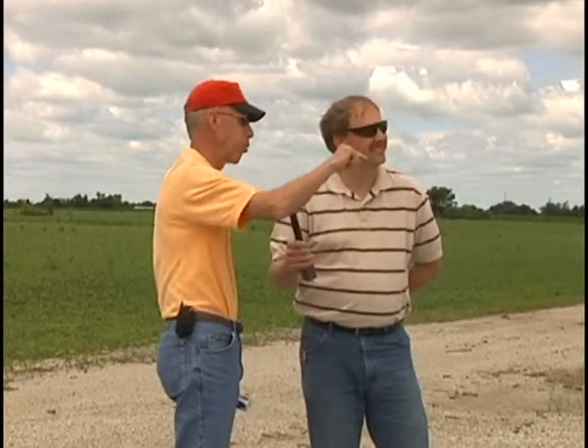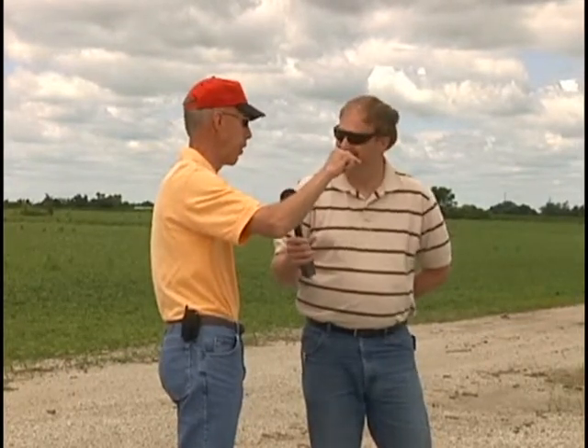And one of the factors is they have to be 1,025 feet apart, away from each other, because they do rotate in the wind. At some time, two towers are going to be in a straight line with each other. I pointed out one of that situation today. There were three of them in a straight line, and the wind was blowing right past all three of them. If that would be the case and they were closer than 1,025 feet, the turbulence from the upwind blade would damage the downwind blades, and the warranty would expire. You'd understand that. Flamini is a physics teacher.